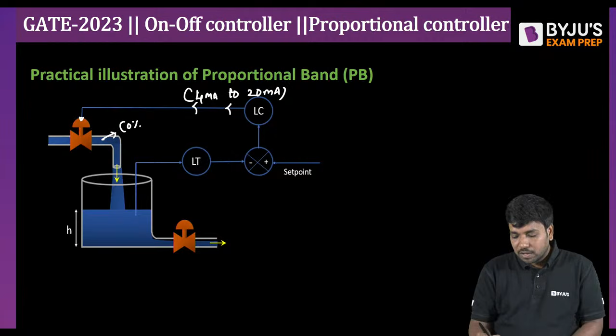And that controller signal comes to the valve here. The valve can either be shut off, that is 0% opening, or it can be 100% open, meaning fully closed or fully open. 0% opening means it is closed. 100% opening means it is fully open, right? What does it mean here? It means that if the controller current is 4 milliampere, the valve will be fully closed. If the controller current is 20 milliampere, it is fully opened.